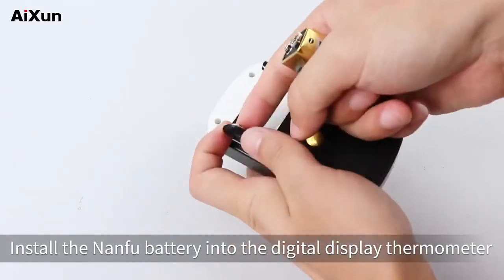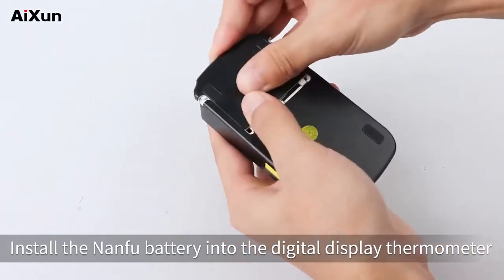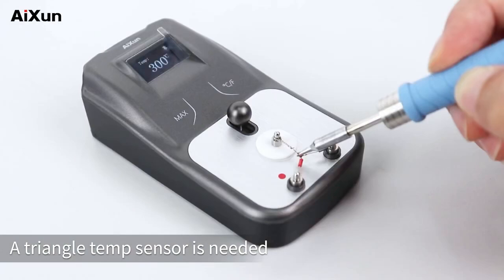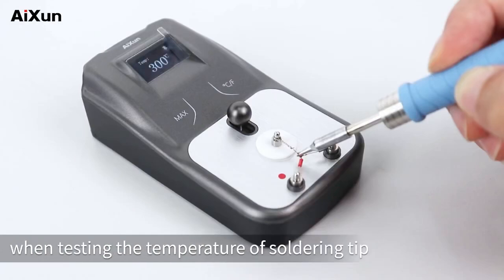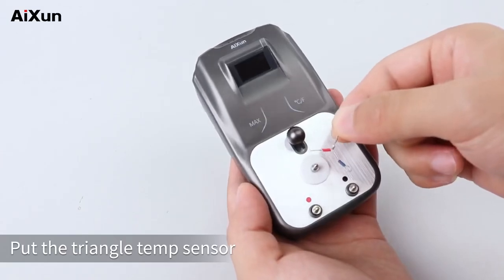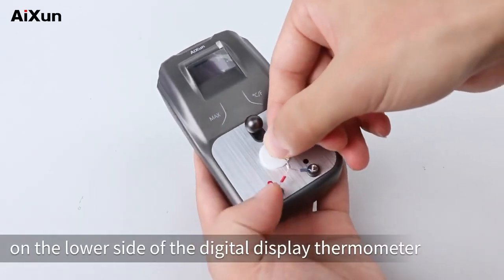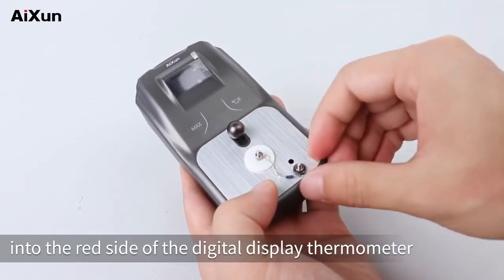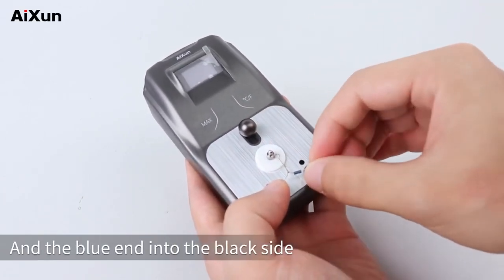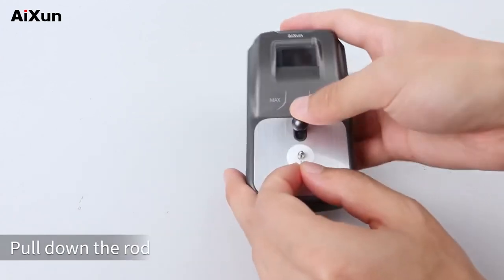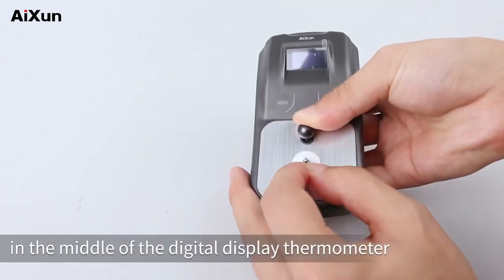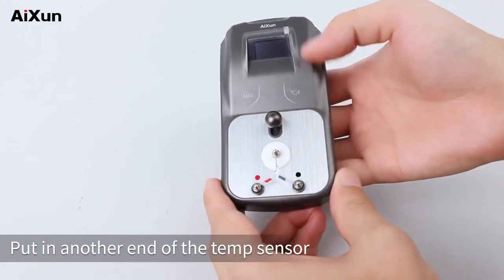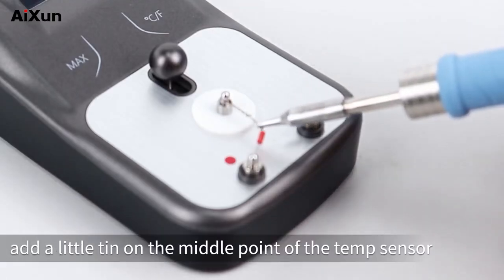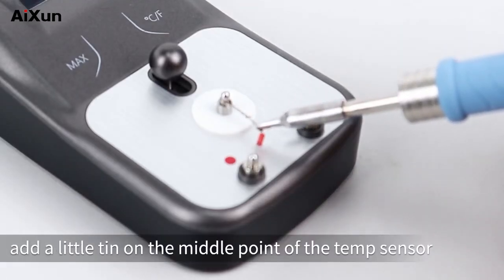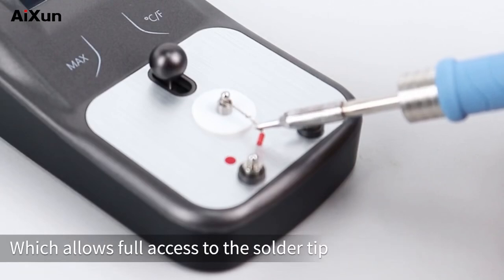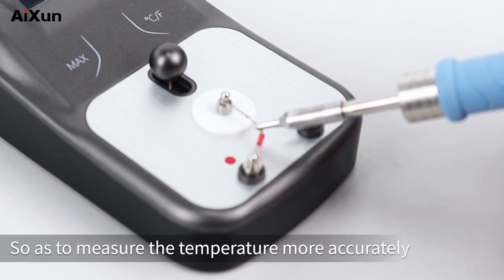Install the Nanfu battery into the digital display thermometer. A triangle temp sensor is needed when testing the temperature of soldering tip. Put the triangle temp sensor on the lower side of the digital display thermometer. Put the red end into the red side of the digital display thermometer, and the blue end into the black side. Pull down the rod in the middle of the digital display thermometer. Put in another end of the temp sensor. Before testing, add a little tin on the middle point of the temp sensor, which allows full access to the solder tip, so as to measure the temperature more accurately.